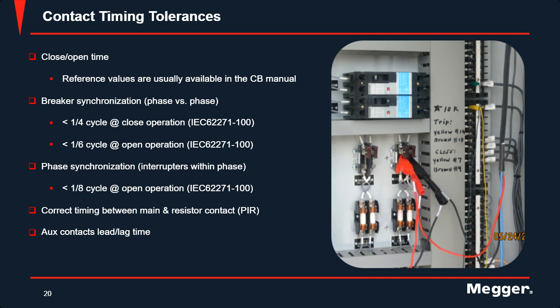You can also do, based off this timing, the timing between your main and your resistor contacts for pre-insertion. You can also do timing on your auxiliary contacts for your lead and lag time. So the resistor contacts can be pre and post insertion. Timing the resistor contacts is done simultaneously with the main contact, so there's no added test there. But the resistor contacts are only detected while the main contact is open. The resistor value is a good parameter for evaluation, based off what the resistance of that pre-insertion or post-insertion resistor should be. As far as the auxiliary contacts go, there are no general time limits for the time relations between the main and the auxiliary contacts, but there is still important information to be seen and understood based off your incoming signals to your auxiliary contacts.